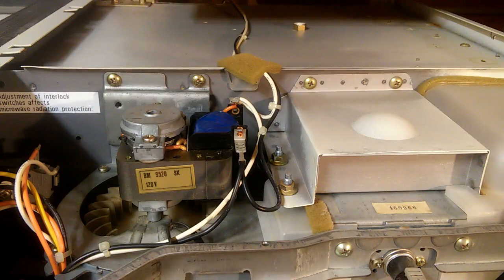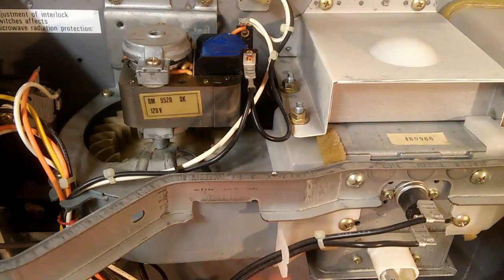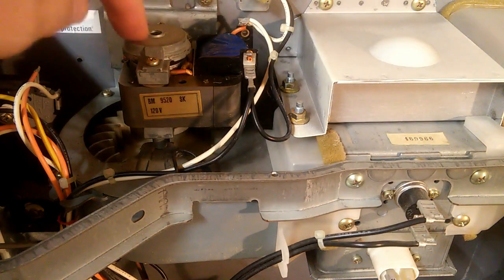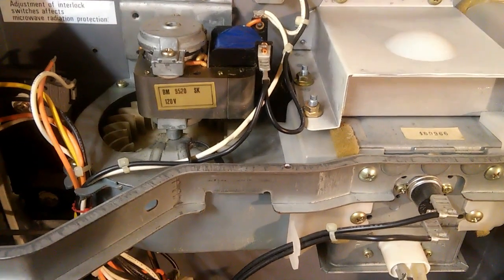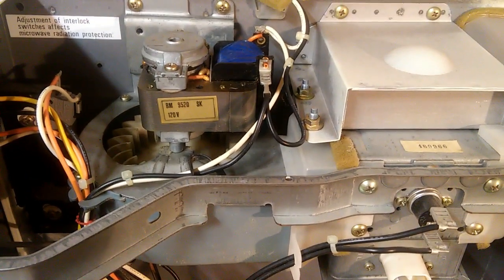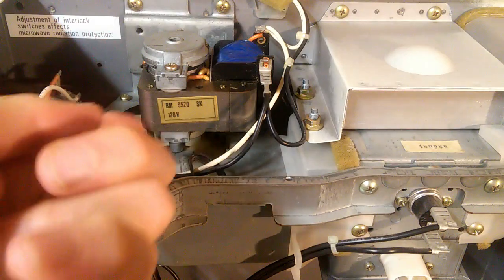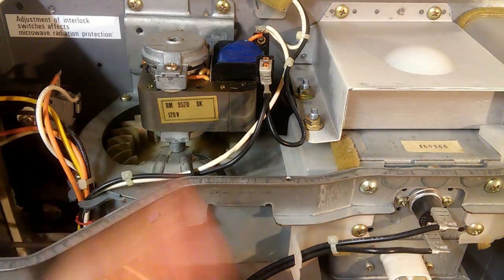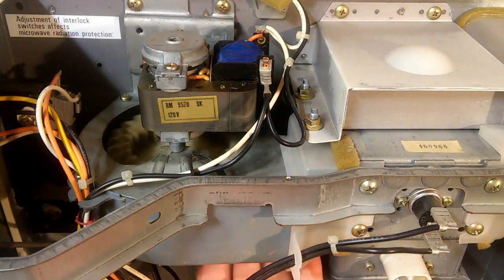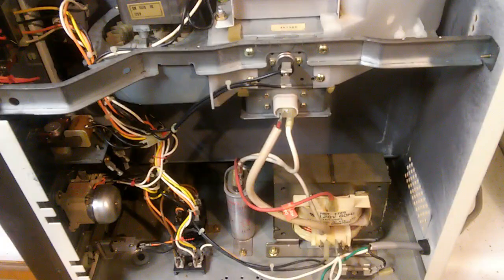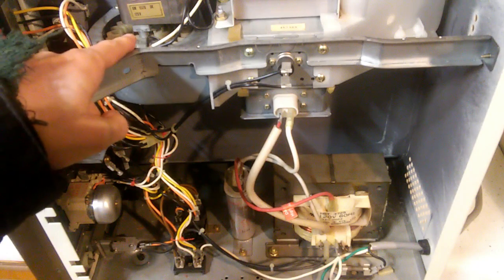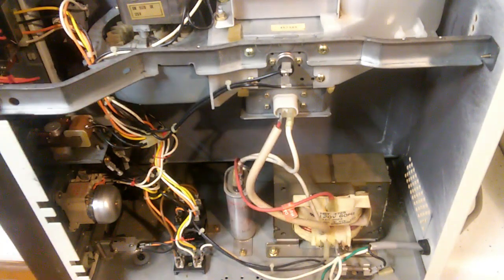So why is it taking so long to turn? Perhaps the bearings are getting gummed up a little, and we need to relubricate them. There's a bearing here, and another on the other side, with the fan basically dangling underneath. What we want to troubleshoot here is why this fan is turning so slowly.